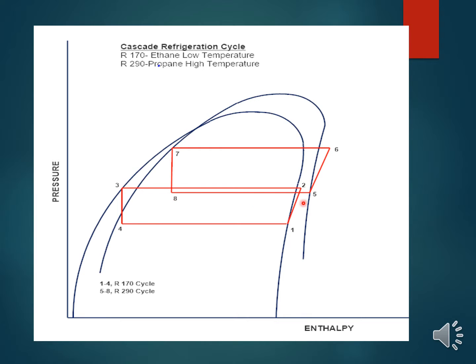From point 8 to point 5 represents the evaporating of the R290 within the interstage heat exchanger. And from point 5 to point 6 represents the compression of the R290. And point 6 to point 7 represents the condensing of the R290. And from point 7 to point 8 represents the expansion of the R290 within the thermal expansion valve. In this area, there has to be a minimum of a 10-degree overlap that causes a sufficient amount of heat exchange within the interstage heat exchanger.